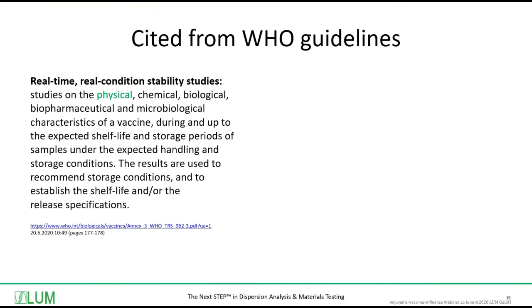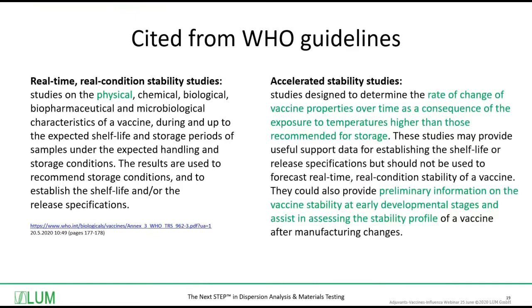For LUM instrumentation, we have a particular focus on the physical characteristics, and if other characteristics influence the physical characteristics, we may also detect those influences. In the WHO guidelines, they also talk about accelerated stability studies, referring to the rate of change of vaccine properties over time as a consequence of exposure to temperatures higher than those recommended for storage. That means we are not talking about physical acceleration by centrifugal force — we are talking about higher temperature.